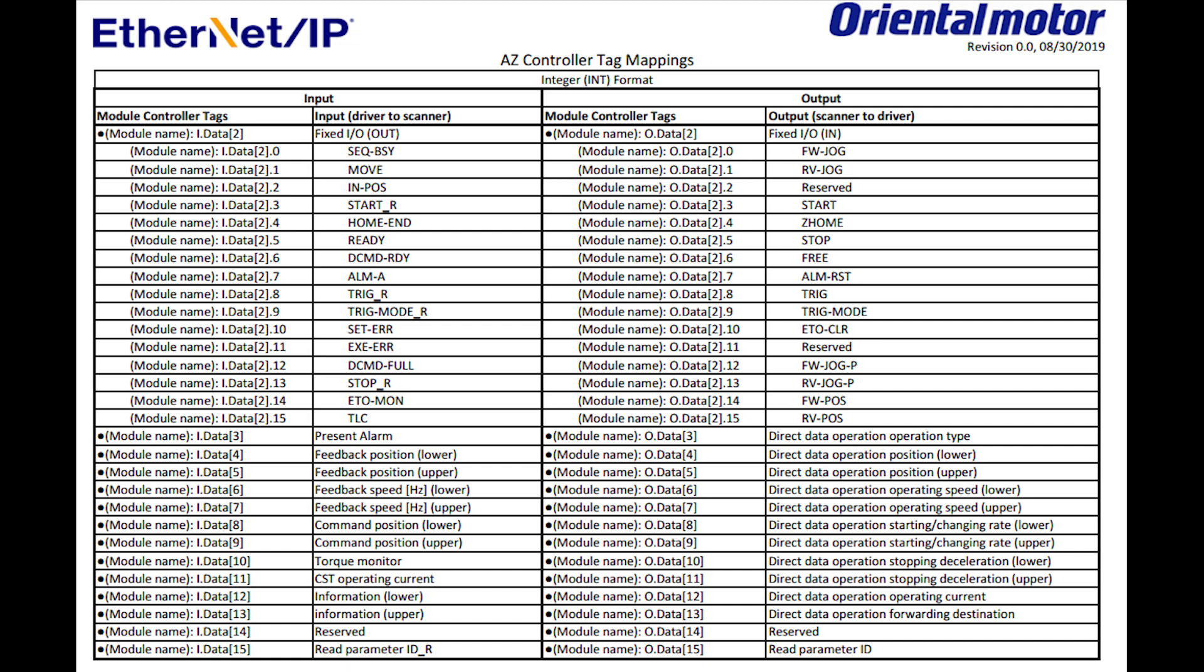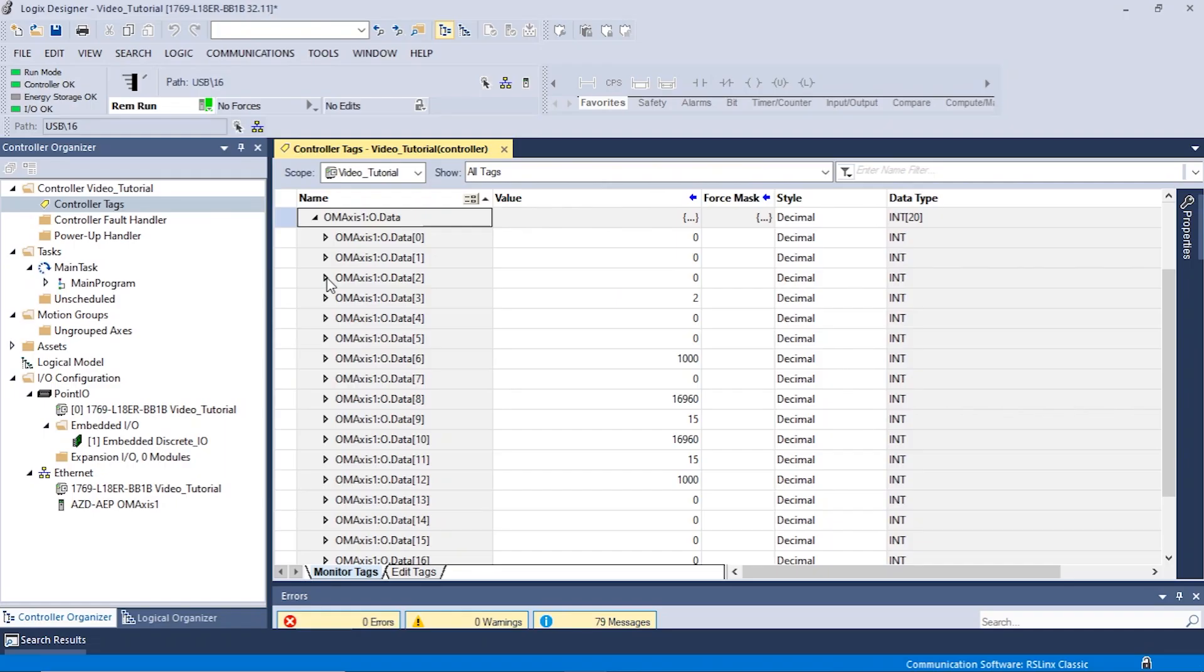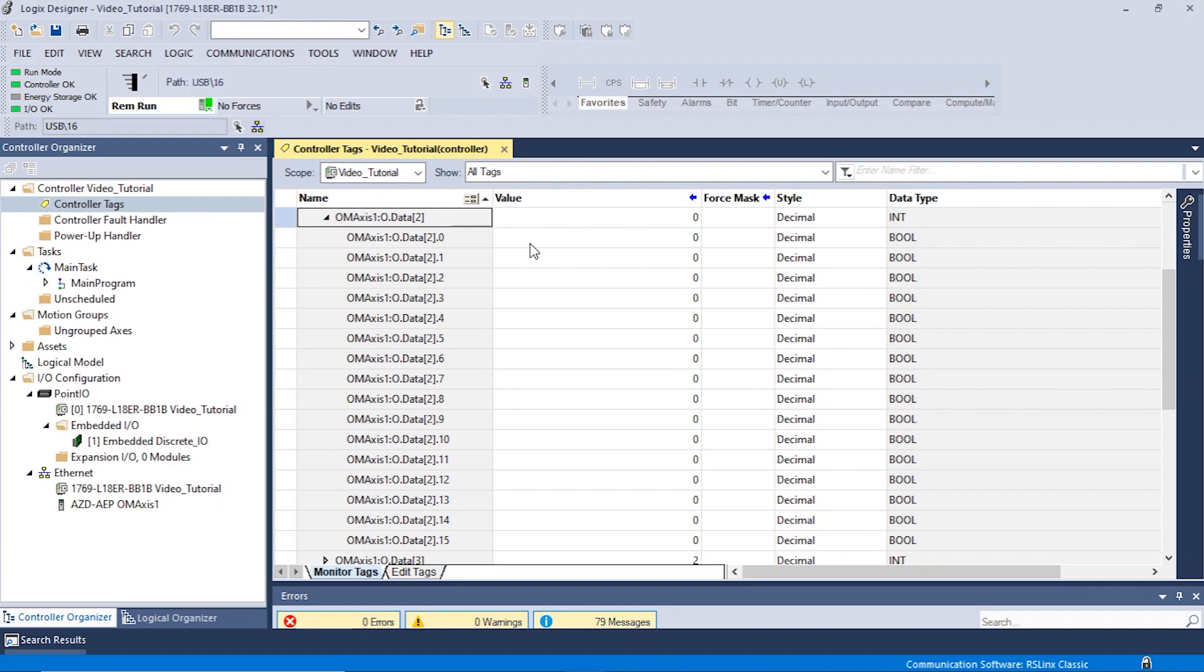In order to jog, we need to activate the forward jog bit. This is located under the output data 2 bit 0. Let's begin by expanding the data 2 and entering a value 1 for bit 0. The motor will now move in the forward direction. To stop the motor, enter a value of 0.